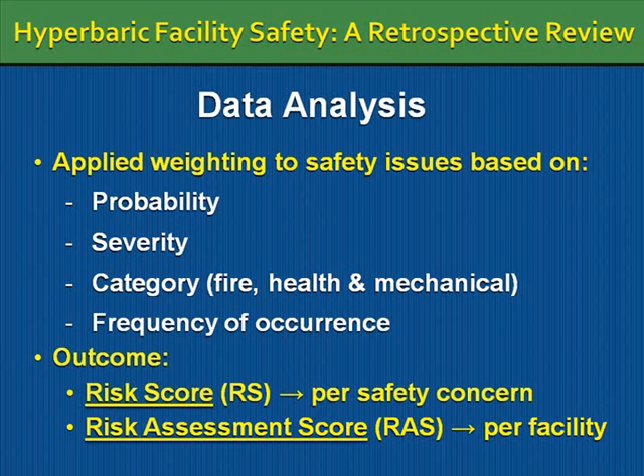So the actual risk of the window is relatively low because from the engineering side, and that's about the only time I can stand up here and say I'm the engineer amongst the engineers, they have done a really great job with windows, and we've had very, very few accidents involving windows, although people tend to be very fastidious about them and very concerned about scratching them. They are not the weak link in the chamber. So we end up with a risk score for each of those 82 different risks as we've looked at.